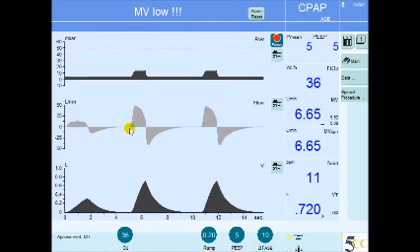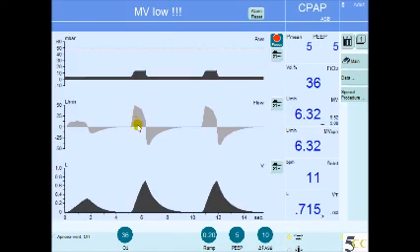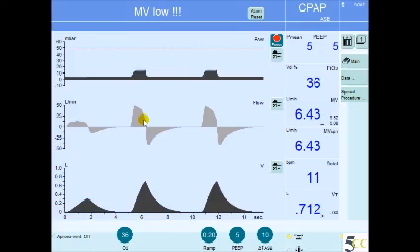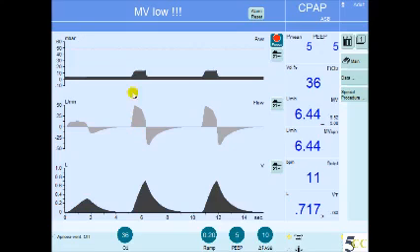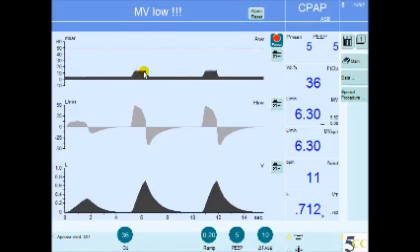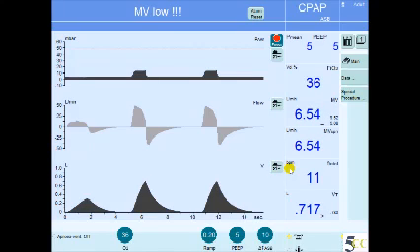A breath that is flow-triggered, pressure-limited, and flow-cycled is a pressure supported breath. The inspiratory time may differ from one breath to another due to variable flow, and the volume is variable depending on the patient's effort. In summary: a breath that is patient-triggered, pressure-limited at the set pressure support level, and flow-cycled at the set percentage of maximum inspiratory flow is a pressure supported breath. If all the breaths are pressure supported breaths, the mode is called pressure support ventilation.